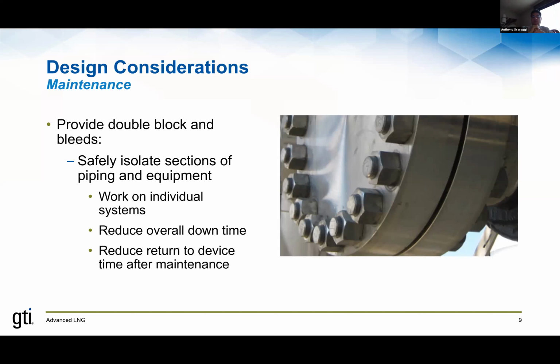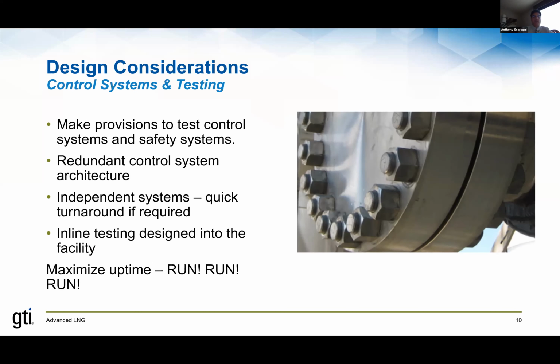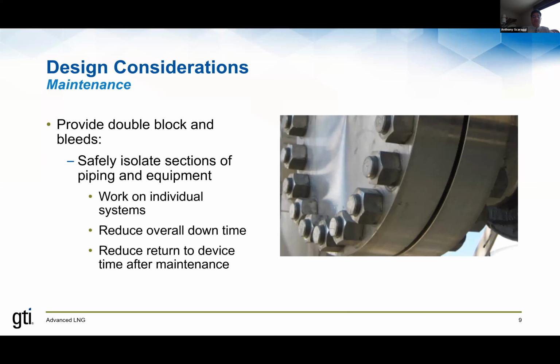And monitoring a double block and bleed, or the bleed on a double block and bleed, lets you know if your valving system is actually operating properly to isolate the source of LNG from the equipment that's being worked on. Placing these double block and bleeds in proper areas, so that you can do maintenance without having to take large pieces of equipment out of service, allows you to maintain a facility safely, quickly, and effectively.